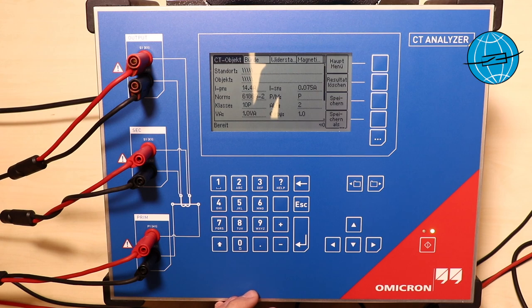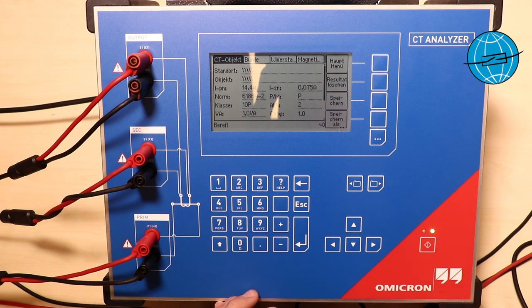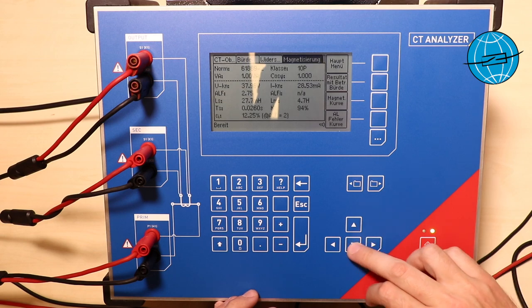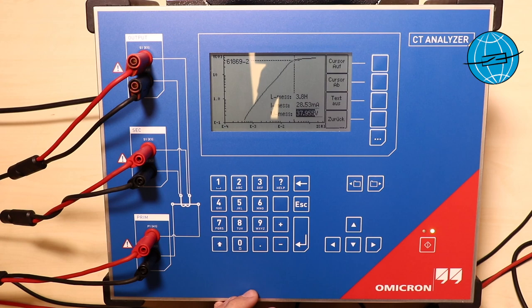And now we are done. The Omicron announces happily the result. Our knee point voltage is 37.955 volts. So let's say it's 38 volts.